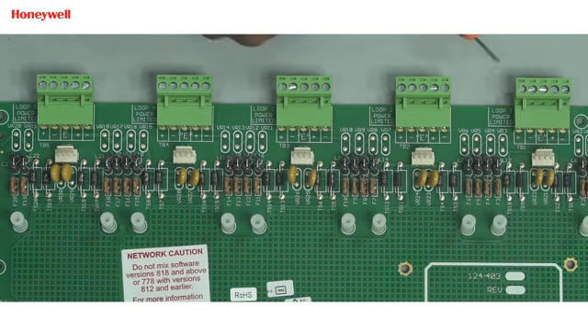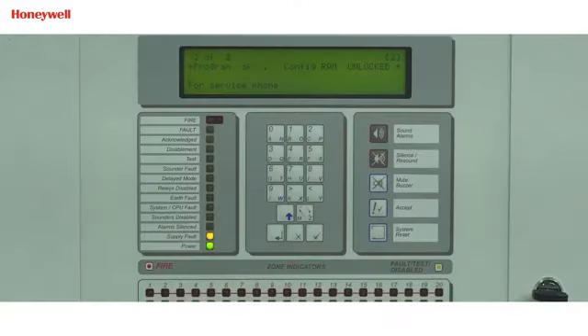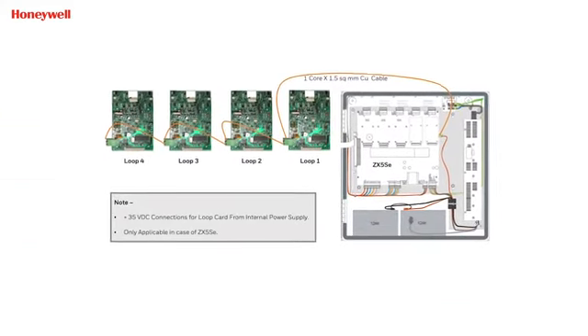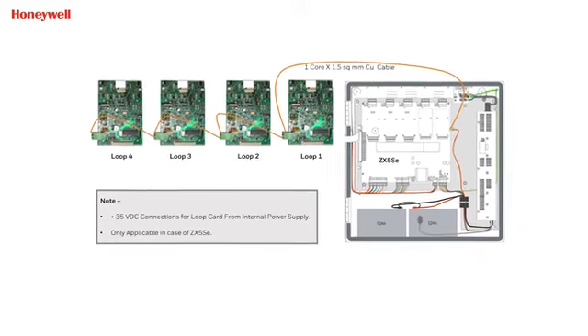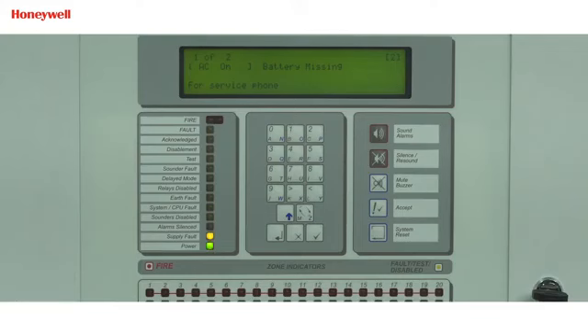ZX5SE has 5 loop slots and installation of loop card at slot number 1 is mandatory. In ZX5SE, 35 volt DC cable at the loop driver card should be connected to all the loop cards. Make sure to use same protocol loop card in all slots. Example, if we are using Morley protocol loop card, then it is mandatory to use Morley protocol loop cards in other slots. It is not possible to program different protocol loop cards in same panel.